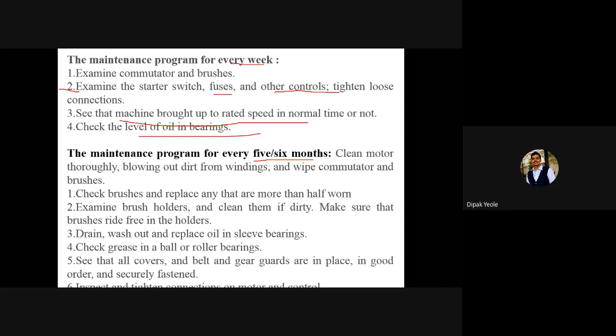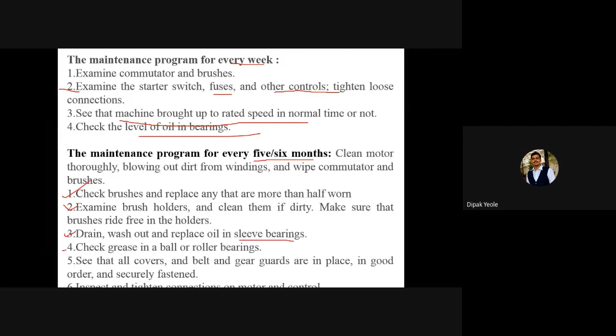After 5 to 6 months, we have to clean thoroughly. We have to check the brushes for wear and tear, and replace them if needed. We have to examine the brush holders and clean them. We have to drain, wash out or replace the oil in sleeve bearings. We have to check the grease in ball bearings. See that all the covers, belt and gear guards are in place, and inspect and tighten connections on the motor and control. What do we have to do after a year?